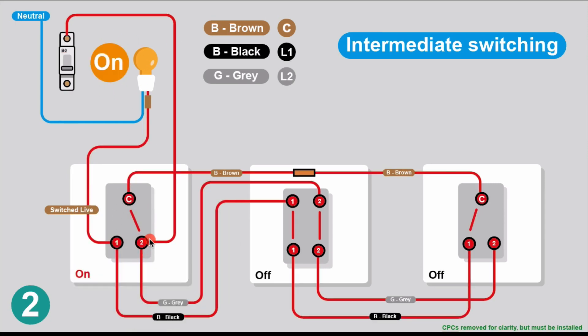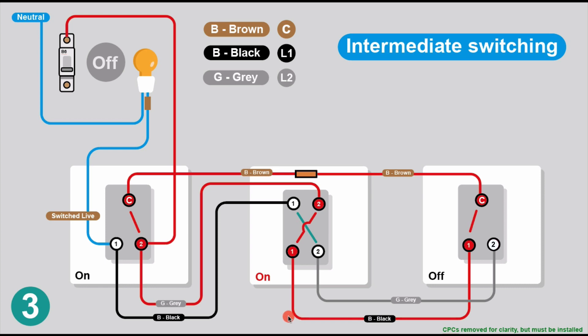We switch the first switch on. Following the power: it comes into the first switch, goes to the common, along through the intermediate, and all the way to the connection on the second two-way switch. Once this connection is energised, the light will be on. Going the other way through the circuit, there's no connection there - but it's being energised by the common. So the light is on.